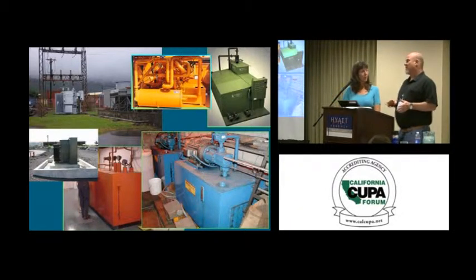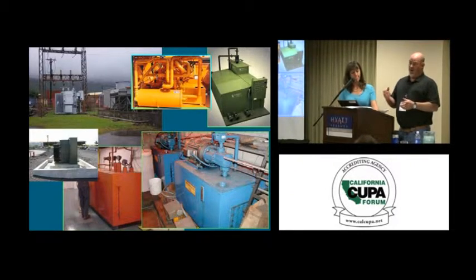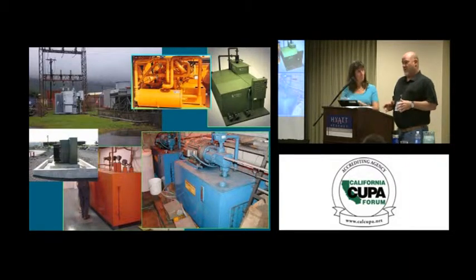You said manufacturing equipment, where that's not going to be subject to sized secondary containment. Only bulk storage is going to be subject to the sizing requirements of secondary containment for containers. If you've got a manufacturing piece of equipment and it's got a process system and the oil's fed into the unit and used within the unit inherent for its function, that's going to stay in general containment requirements.